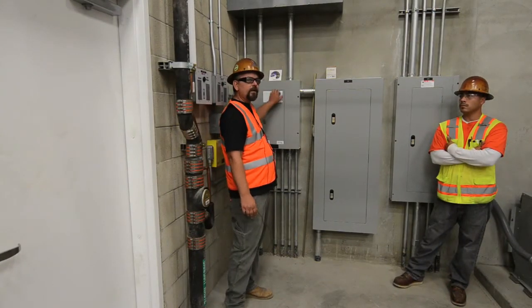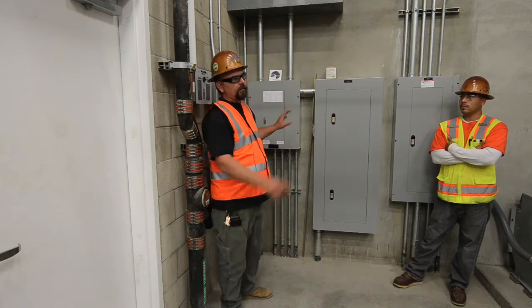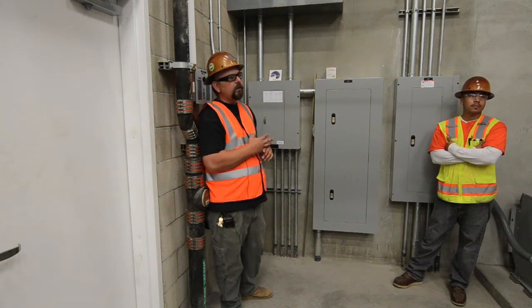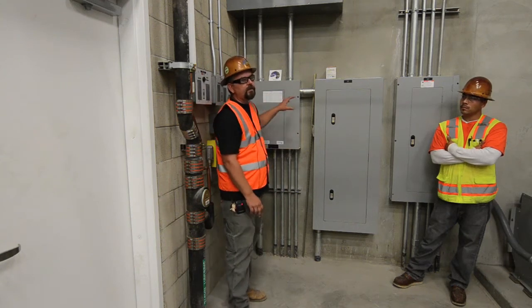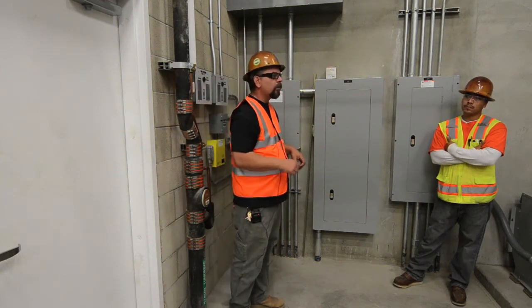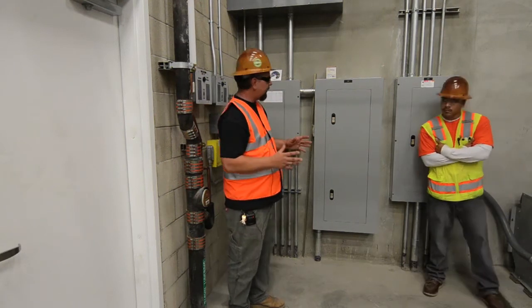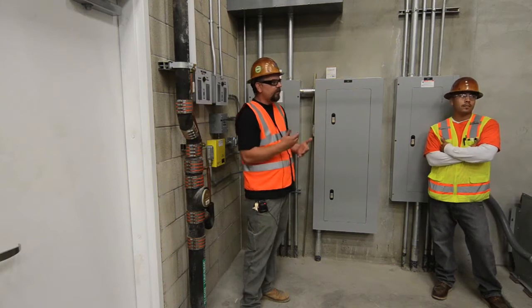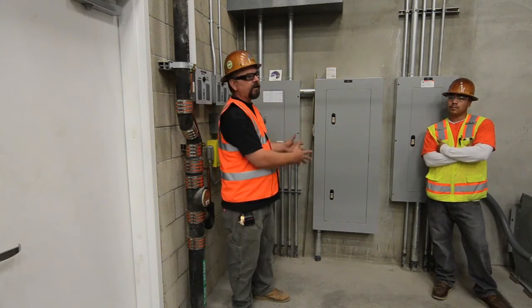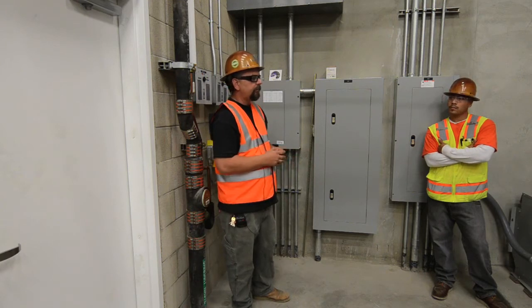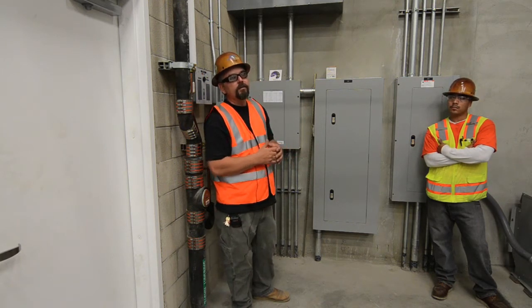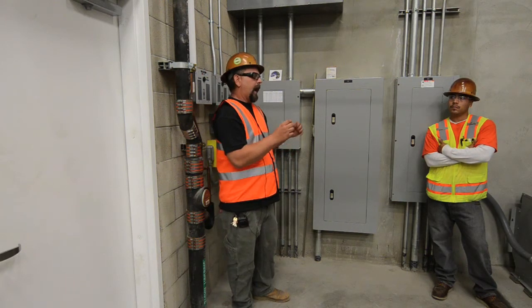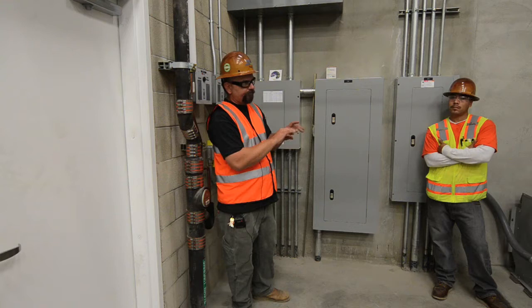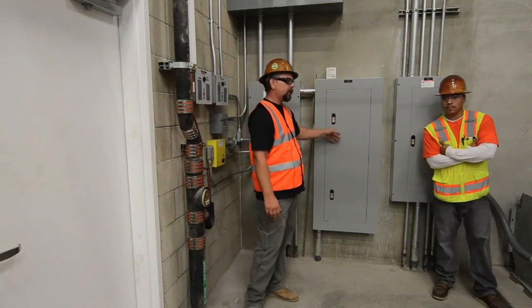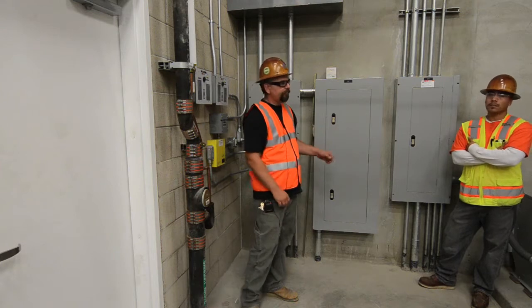I talked to a couple of the guys yesterday. What I've done is installed a permanent panel schedule on here that you guys can't remove. I'm going to be emailing those to Jose and Alfredo, not only the lighting control panel schedules, but the panel schedules for the whole project. So that if for any reason, you know how it is, sometimes somebody takes one out because they need to check something, and next thing you know you're back in the room and there's no panel schedule. The other purpose for emailing you those electronically is so that if you add or change things in the future, you can alter them and have a nice, neatly printed panel schedule in your panels that you guys can maintain.